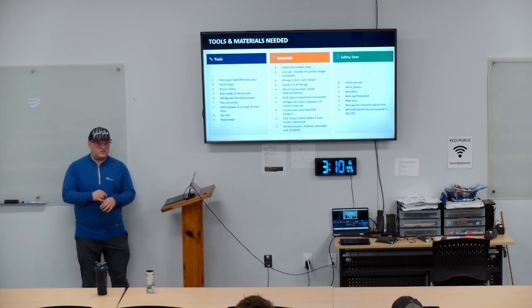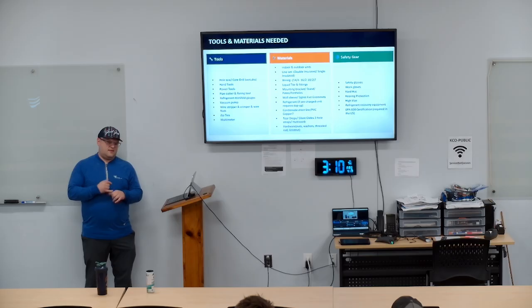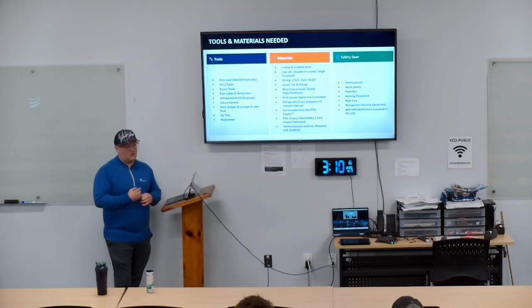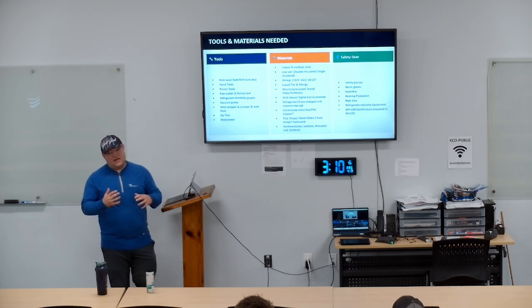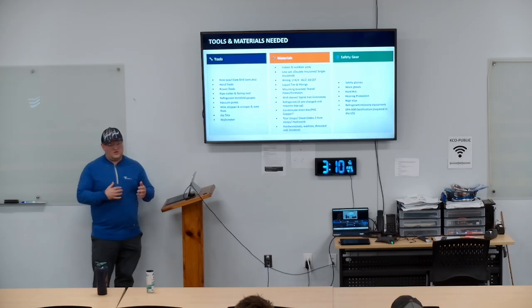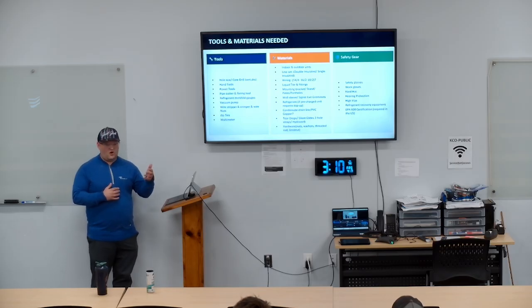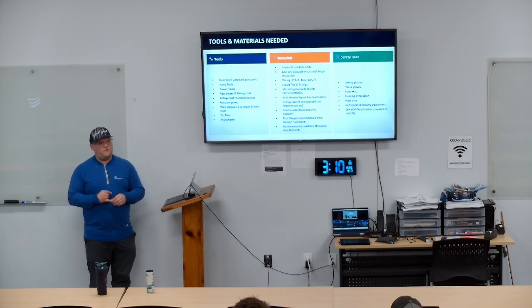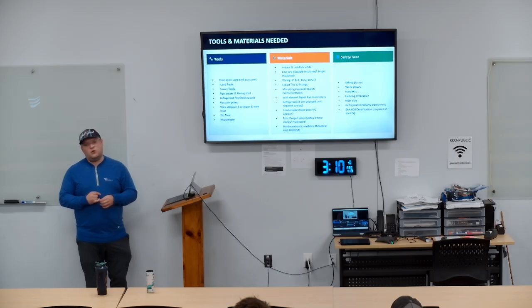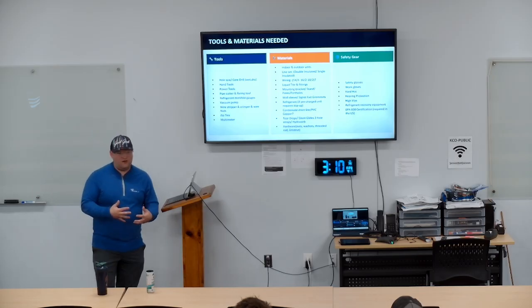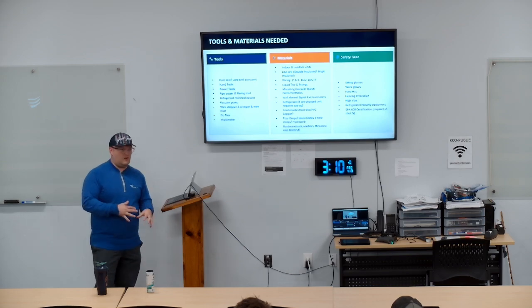but I just saw a change in that with, I can't remember the manufacturer, someone had a 12,000 BTU unit. It was a 1-ton wall mount, and it had a control wire, 18/2. So again, the IOM is where you find that. You can look at a submittal, and I'm not telling you you can't go off submittal. I'm just telling you to verify, because if you don't, it could burn you. I will tell you, it burns us frequently.